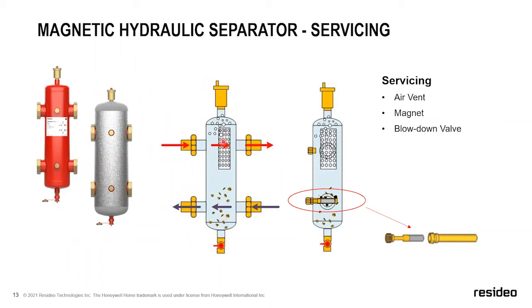So what happens is if you want to service it, clean it out, because again, you've got magnetic materials that are sticking to the magnet, you've got dirt and sediment that's fallen down here. All you have to do to service this on a regular basis is one, check your air vent, make sure it's operating. And then two, put the system in idle. Make sure there's no pumps running, give everything a second to kind of settle.